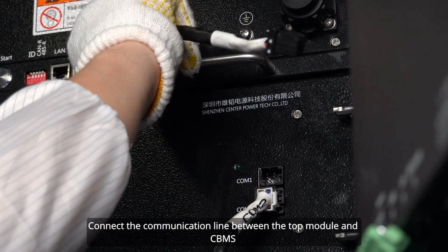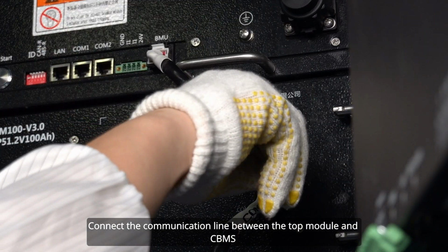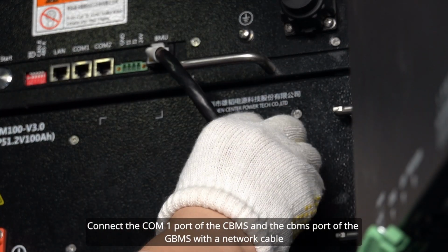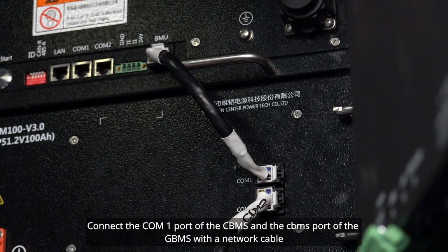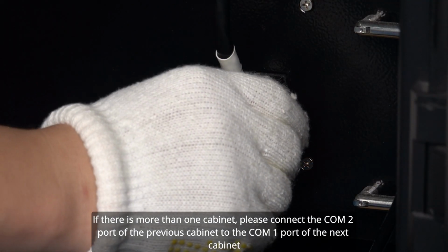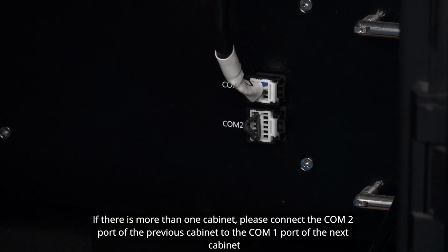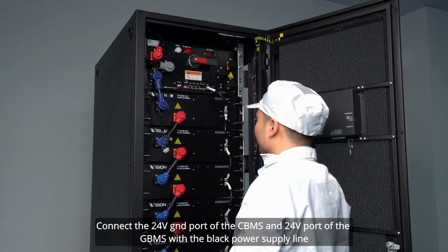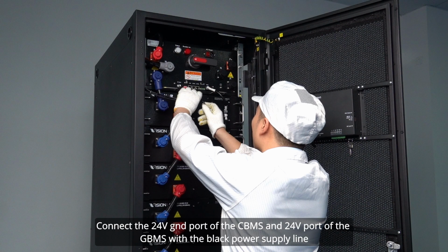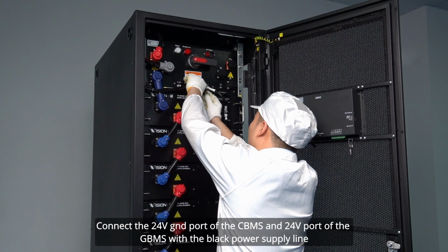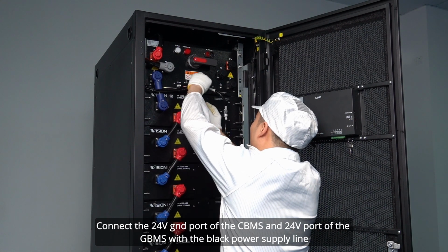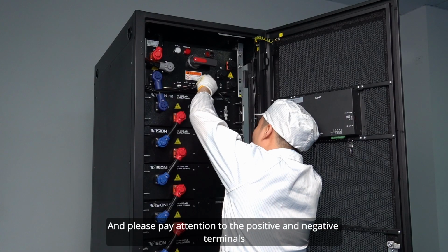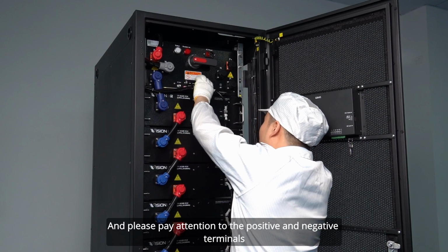Connect the communication line between the top module and CBMS. Connect the COM1 port of the CBMS and the CBMS port of the GBMS with a network cable. If there is more than one cabinet, please connect the COM2 port of the previous cabinet to the COM1 port of the next cabinet. Connect the 24V GND port of the CBMS and 24V port of the GBMS with the black power supply line. And please pay attention to the positive and negative terminals.